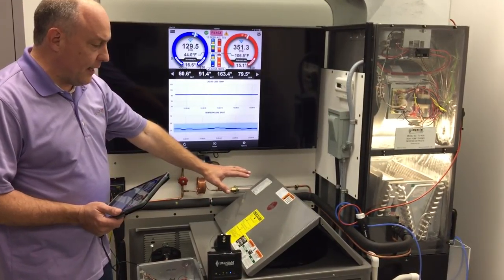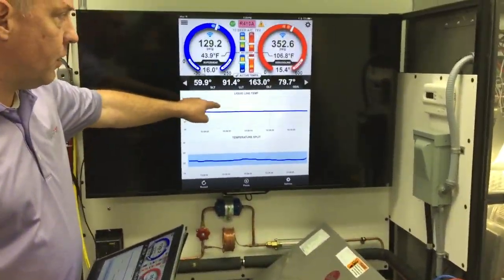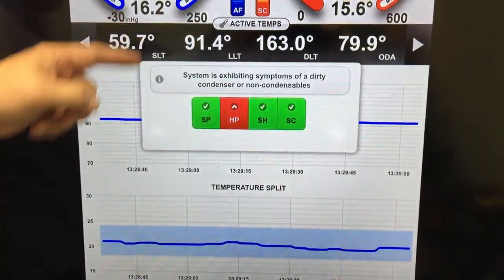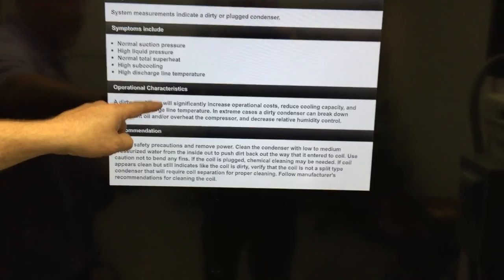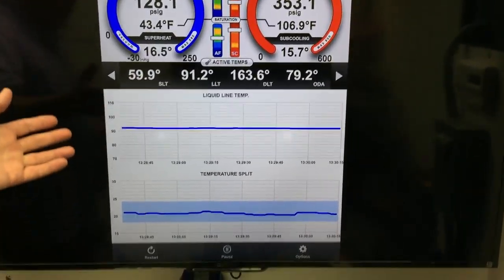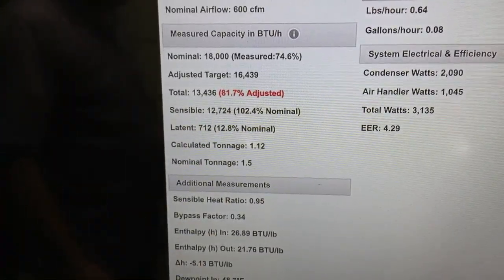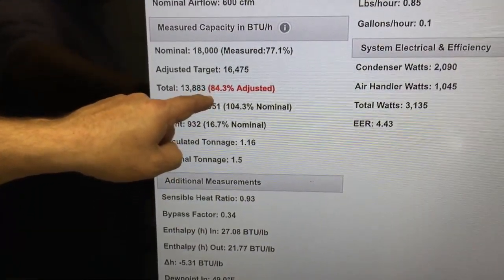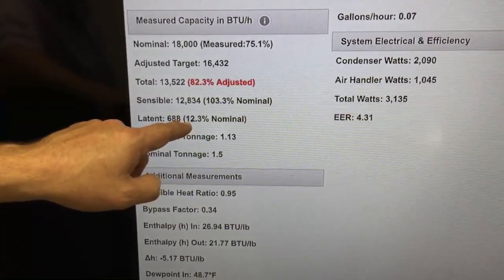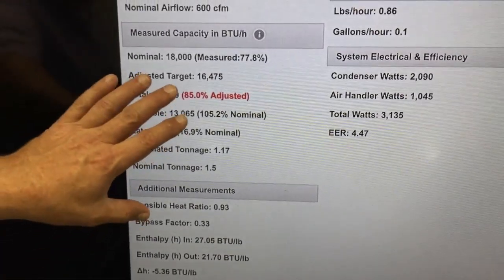Right now what I've got is our little lab unit here set up. I just sort of threw the condenser door over just to get the pressure up a little bit. You can see our temperature splits right in range, our liquid line temperature stable. If I ran troubleshooting on the iManifold application, you can see it's exhibiting symptoms of a dirty condenser. Typically what we do is just clean that condenser because it's going to increase the operational cost, so it's pretty straightforward, but not a lot of effect on the capacity or loss. In fact, if we go into performance for a minute here, you'll see it's doing about 102% of its rated sensible capacity. This is pretty normal that it's doing this low total capacity because we don't have any latent load to remove. It's extremely dry in here right now, so we're only removing about 17% of our nominal latent capacity, but pretty normal. Let's see how it affects the sensible.